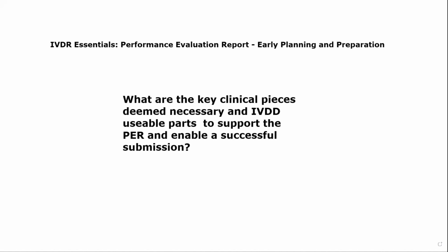So within IVDD, you still had an SOTA section, or at least the beginnings of a SOTA section. You may have presented the clinical scenarios by which your device is used and things like that. But IVDR is holding you to a higher standard in that it needs to be very well documented. It should be appraised, and the whole methodology for developing these searches should be very well documented and described. You're also expected to have that landscape section, which I'm finding a lot of IVDD documents are not really fully what they're expecting to see in terms of the landscape analysis and properly identifying competitor devices.